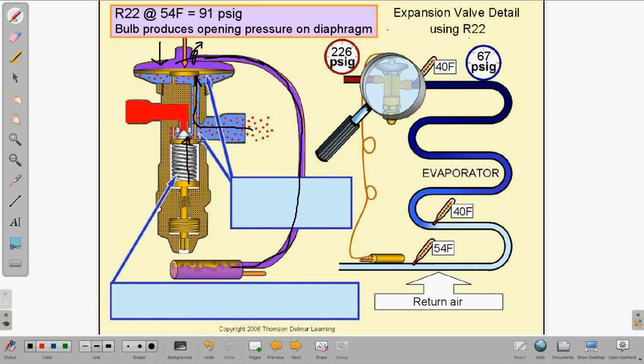evaporator for refrigerant. Now these valves rarely slam all the way closed and block off the refrigerant, nor do they open up 100% to let the 100% refrigerant go through. There's a range that it operates. So when the sensing bulb loses its charge and there's no opening pressure, the spring pressure and the evaporator pressure don't close this seat all the way. It just starts to starve it for refrigerant, and what you'll find is all the pressures will be good as far as charging, and the charge will be correct, but as it's going through this tiny little opening right here, it'll start to freeze up this valve, and it'll start to freeze the evaporator coil going down the line, usually about halfway down, and it'll be an iced up TXV and an iced up evaporator coil. It's a pretty sure sign.